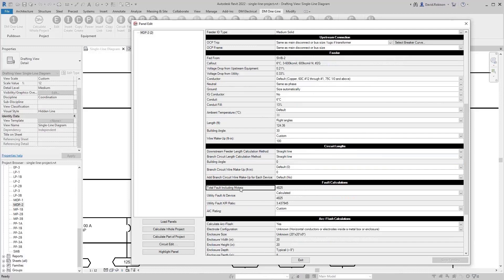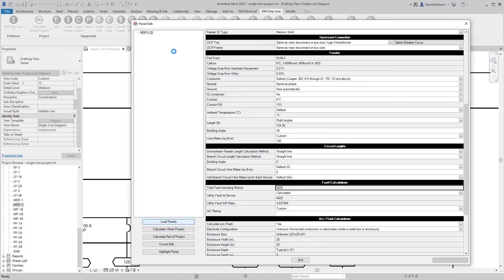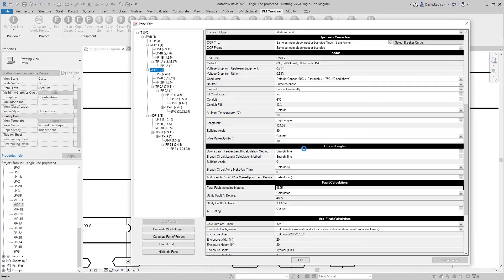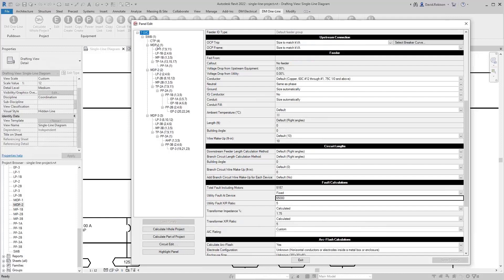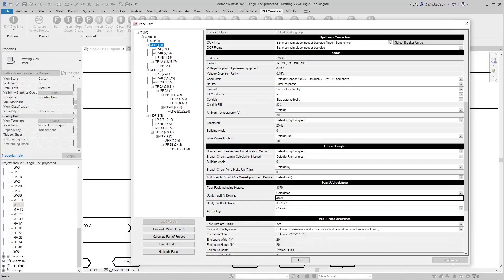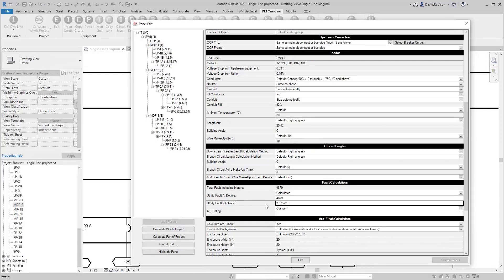Below that we have the fault calculations. We list the total fault at the device including motors — anything marked as a motor is included in the fault calculations. You can set the utility fault; typically you'll get this from the utility and specify it as the basis for the calculation. For the service transformer you can set a fixed utility fault. You can also specify the XR ratio — it gives a default value but you can override it.